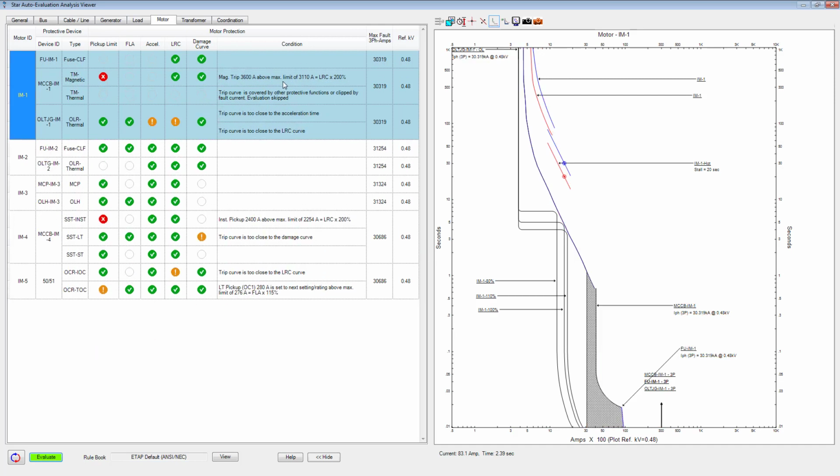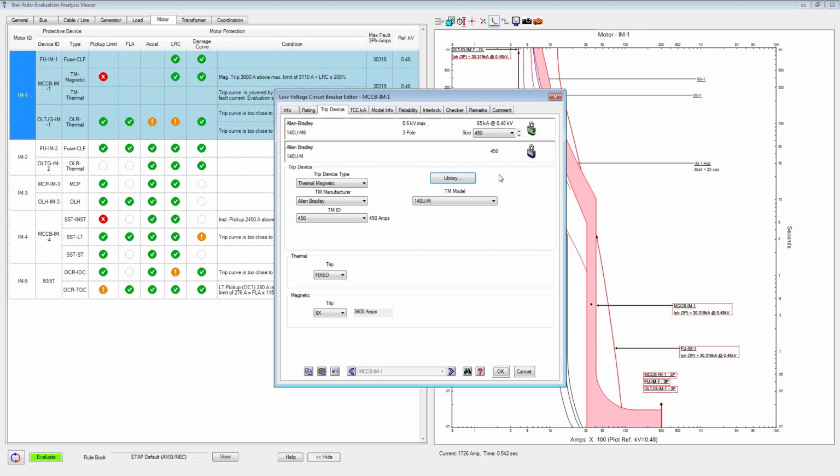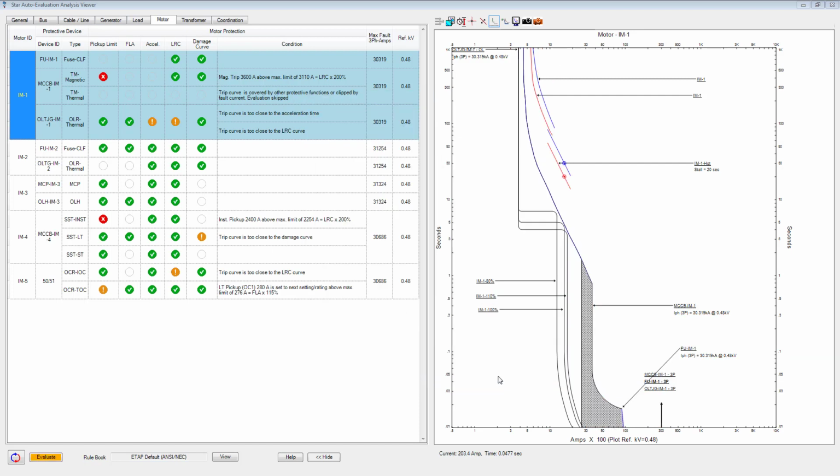but you see the magnitude of the value is 3600 and still it is above 3110. So this magnetic setting has discrete settings, so you can only go between 7 or 8, and if you select 7, again you would overlap with the, and still it is high.